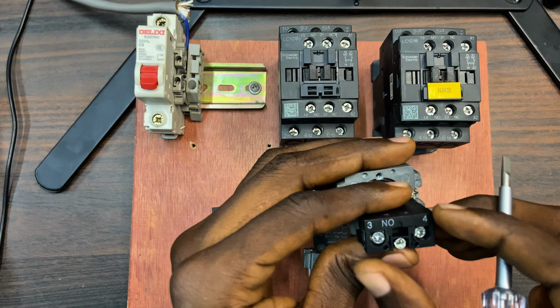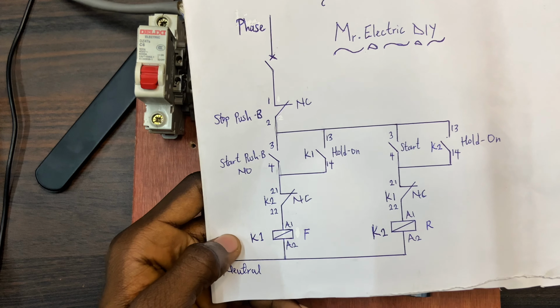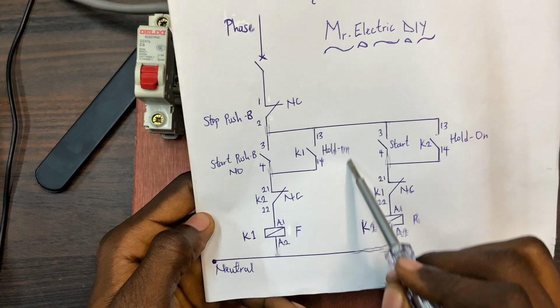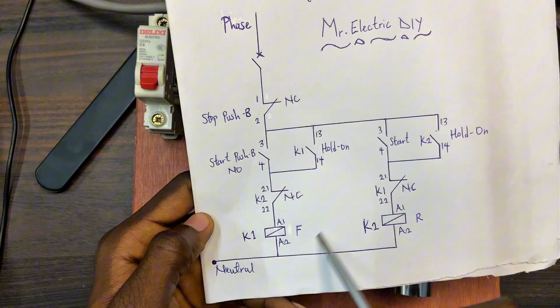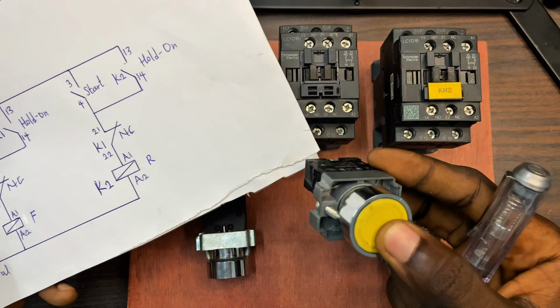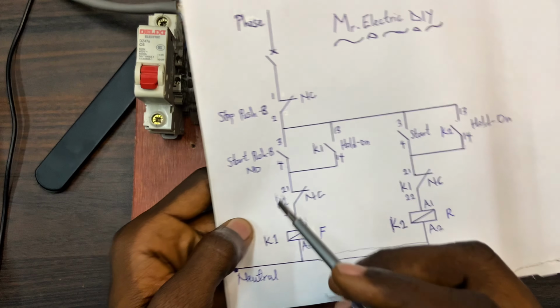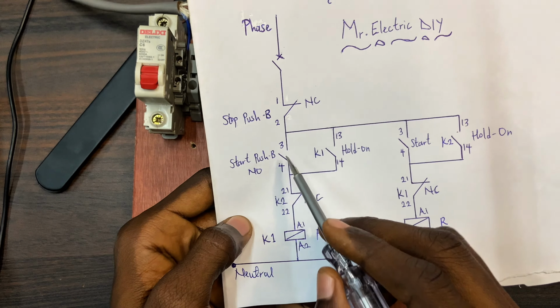And over here is the wiring diagram. We have this as the circuit breaker. This is the circuit breaker. This is actually the phase. And down here, 1 and 2 are the normally closed switch. This is the normally closed for the stop. We have 3 and 4. This is the start push button for the forward contactor. Now look at this. The whole of this place is for the forward contactor, and this side is for the reverse contactor. And as I said, this is the start push button for the forward contactor. You have it at this place, the 3 and 4. And this side is the hold on.